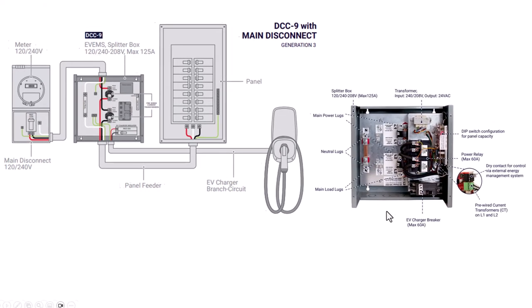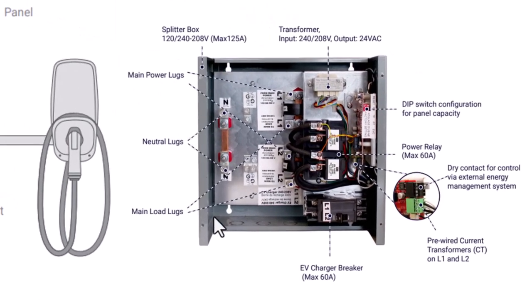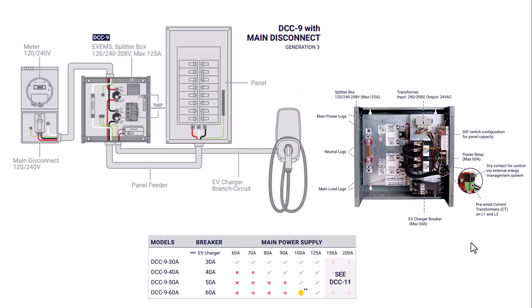So this is the actual picture of the internals of the box. And you can see that the relay is right here. And the relay is what switches the power from the EV back to the main service. And then here is the EV charger breaker right here.